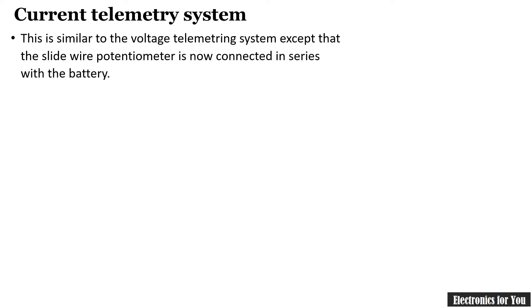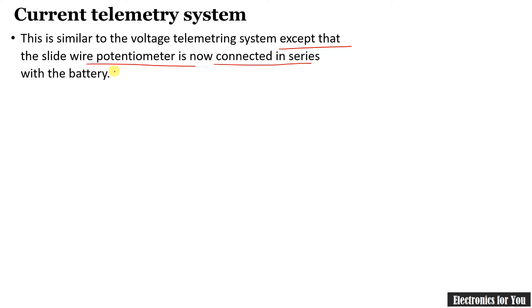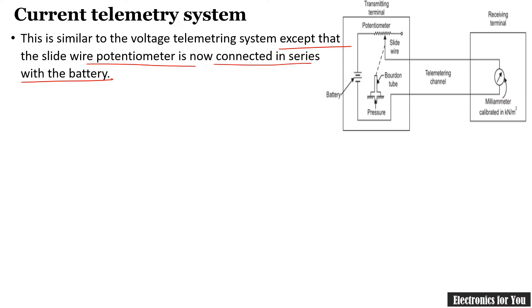A current telemetry system will provide the output in the form of current. It is similar to the voltage telemetry system except that the slide wire potentiometer is now connected in series, because in the previous circuit it was connected in parallel as we were measuring voltage. In the current telemetry system, we are measuring current and therefore the potentiometer should be connected in series.